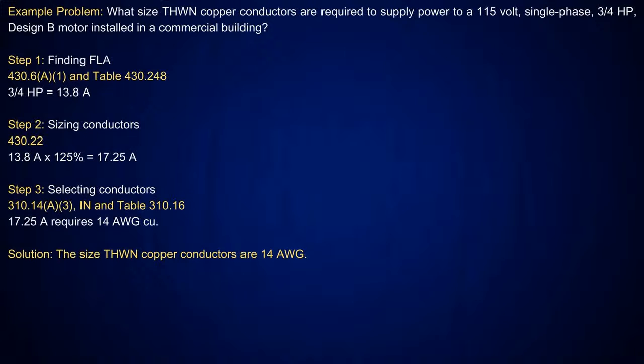Now, if I have multiple motors here, you take the largest motor at 125%, and all the rest of the motors are at 100%. Okay? Now, for this one, 13.8 amps times 125% gives me 17.25 amps. The next size above that for table 310.16 in the 75 degree C column is a number 14 conductor. Simple.